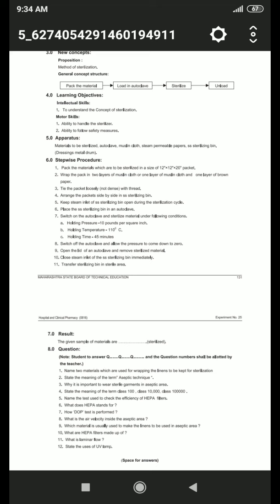Then how is the DOP test performed? DOP means dispersed oil particulate. DOP testing, also known as filter integrity testing, is the process in which the integrity of your HEPA, that is high efficiency particulate air, or ULPA, that is ultra low penetration air, filter is challenged by introducing particulates and measuring the output.